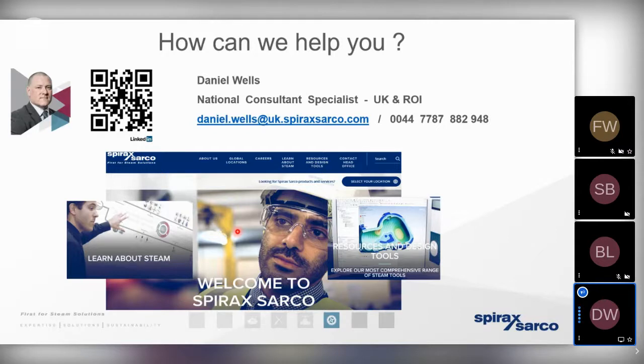And the good news is steam-using sites will already be doing that on a daily basis as part of the HSE BG01, BG03 requirements. So if you spoke to the boilerman or the boiler operator, he'd be able to give you a percentage condensate return. If it was significantly less than 80%, then alarm bells should really be ringing, because there's a huge opportunity there to optimize the amount of condensate coming back and enjoy a significant cost saving.